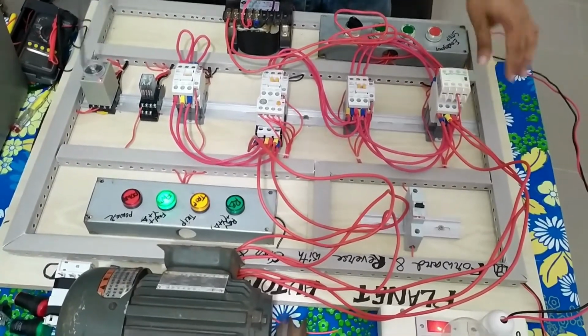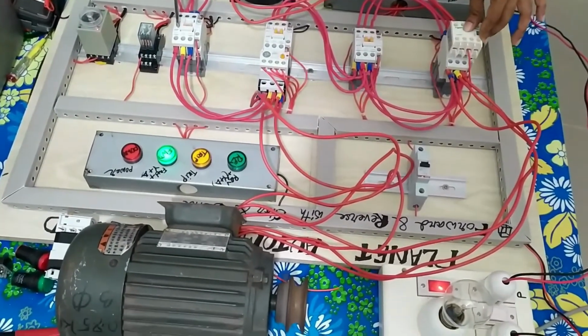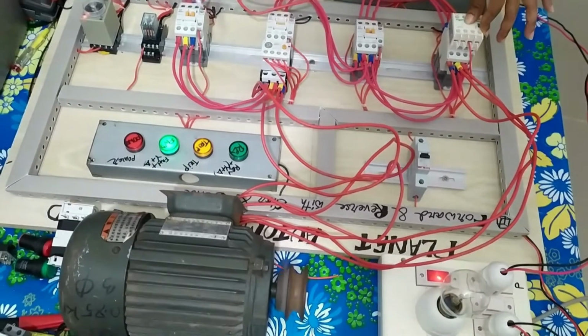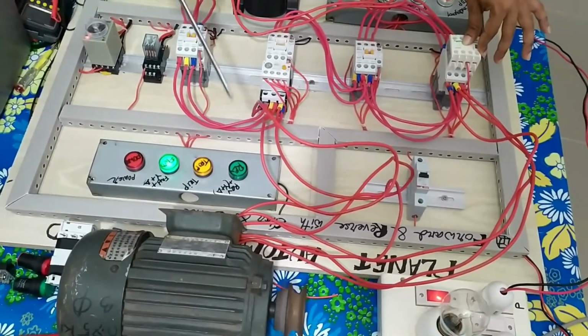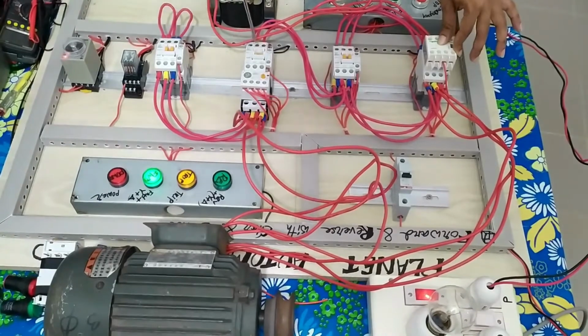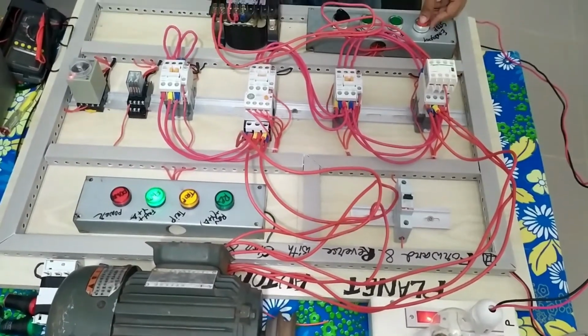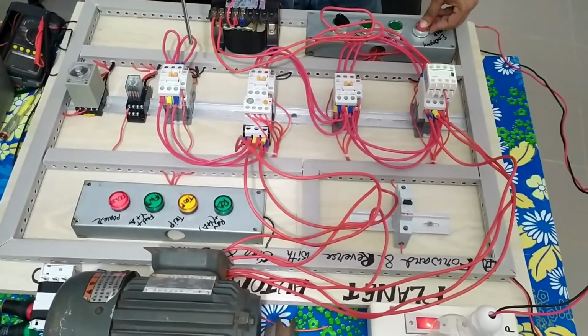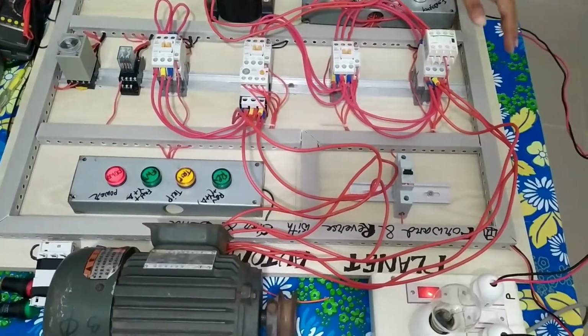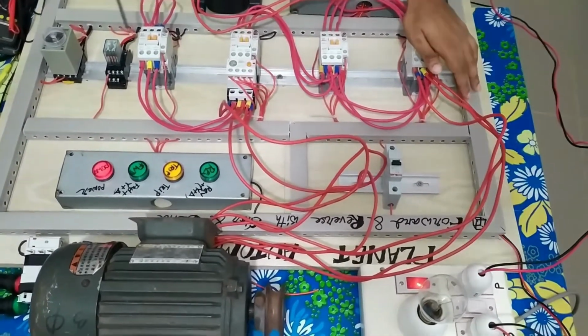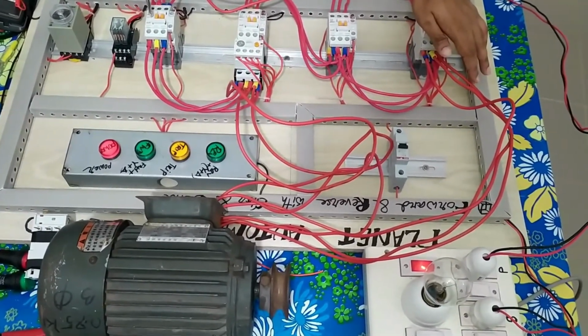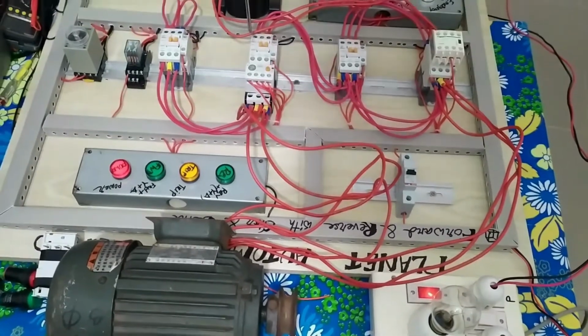After 20 seconds, the star will turn off and delta will be running. Now, after 20 seconds, star is off and delta is on. I want to stop these forward sections. As you saw before, this is the forward reference. Initially the star goes on, and then after 20 seconds it switches.